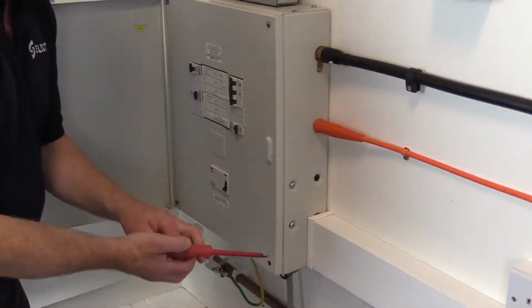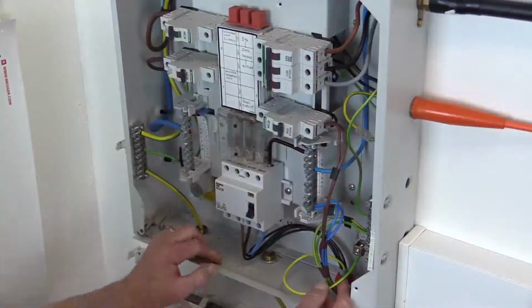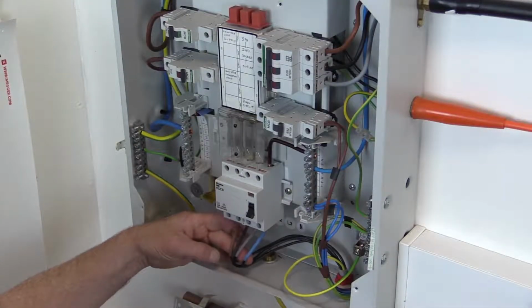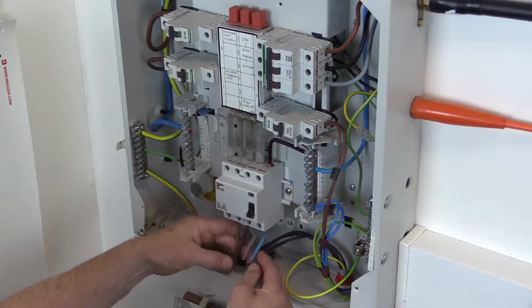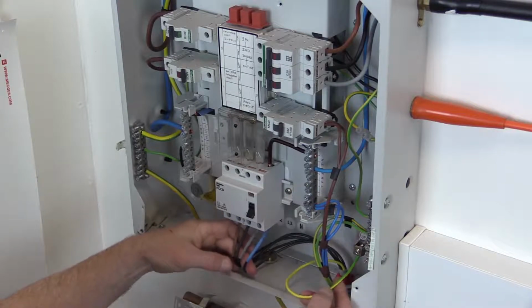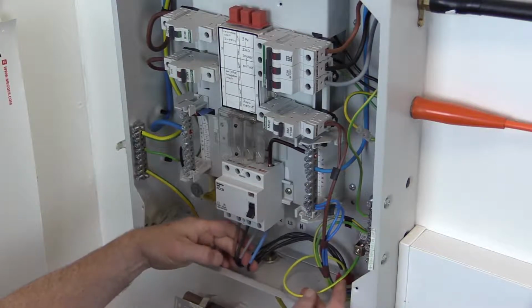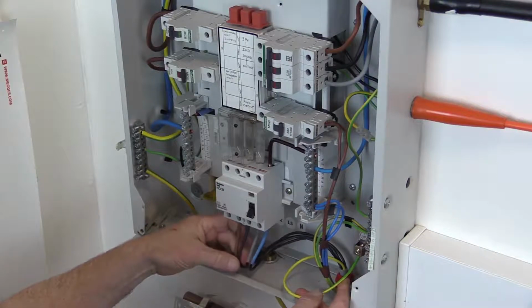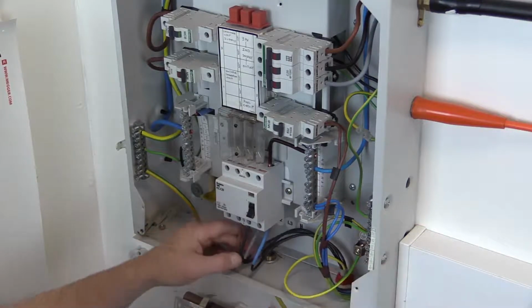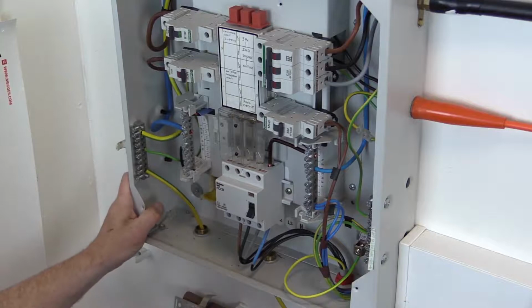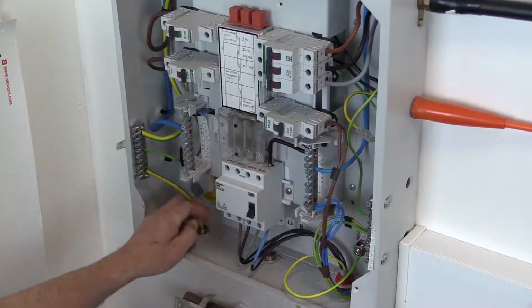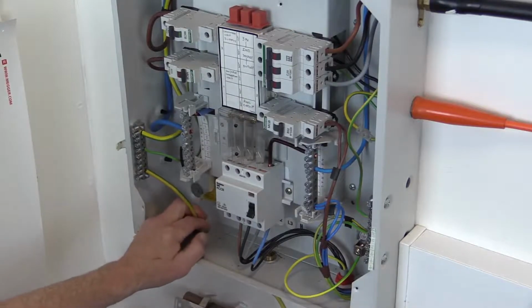From a visual examination of the test rig, it's supplied by a flexible cable taken from a three-phase and neutral supply, TPN AC supply. The supply cable provides a connection to earth using a separate protective conductor, so would be regarded as a TN-S earthing system. The earth fault loop impedance and prospective fault current will need to be determined by test.